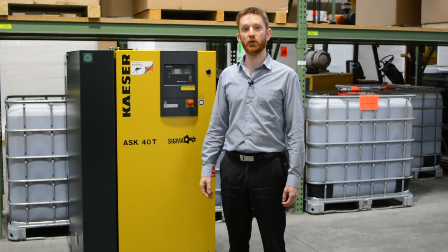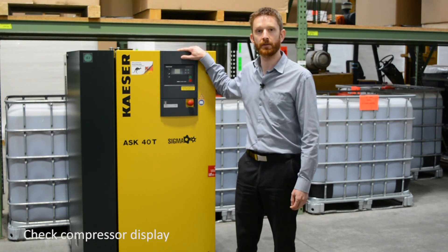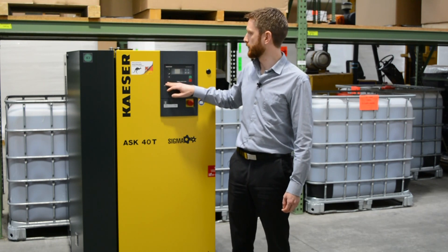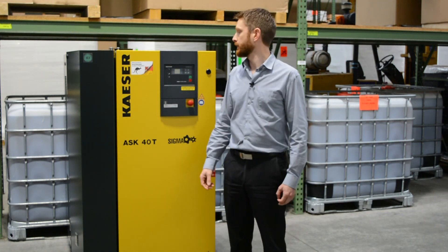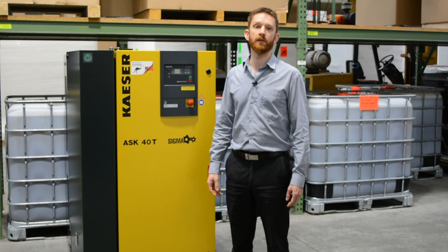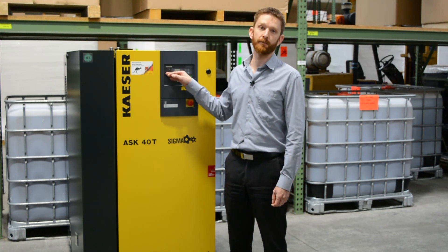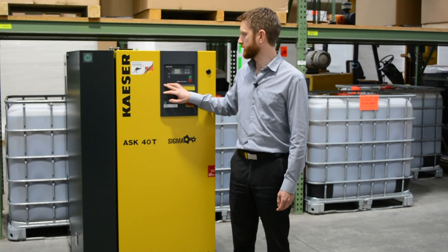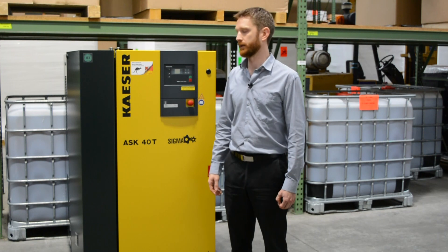Initially for daily checks you probably want to glance at the controller. Most compressors like these have some sort of smart controller, and the Kaeser in particular has a traffic light system. If there's no lights or a green light, that means it's healthy. If there's an amber or orange light, it means there's a warning — it could be due for service or getting a bit warm. A red light means there's an alarm and something urgently needs attention. You can also check the display — it'll flag up if it's due for maintenance, and you can see the oil temperature on there as well.